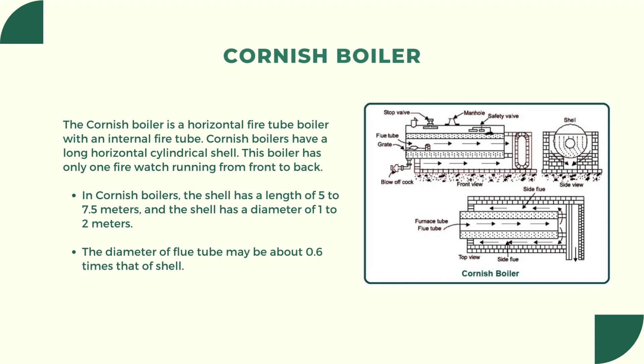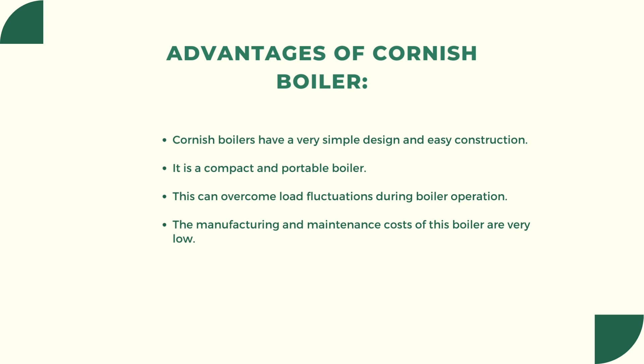In Cornish boiler, the shell has a length of 5 to 7.5 meters and shell diameter is 1 to 2 meter. The diameter of flue tube may be about 0.6 times of that shell. Now, the advantages of Cornish boiler. Cornish boiler is very simple in design and easy in construction. It is a compact and portable boiler. This can overcome load fluctuation during boiler operation. The manufacturing and maintenance cost of this boiler is very low.